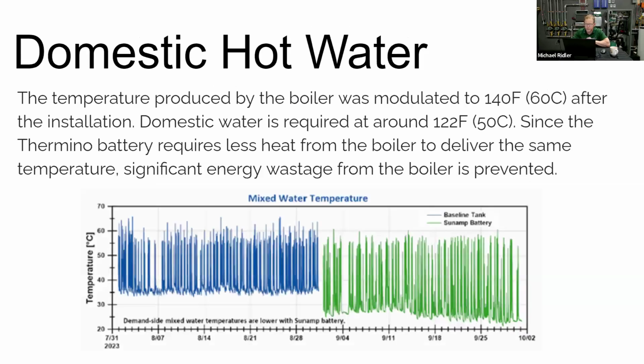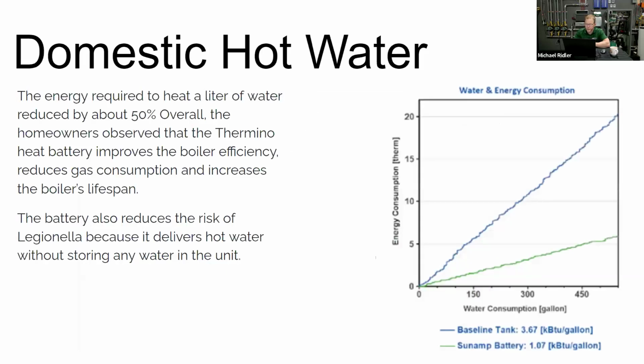If we go on to the next graph, we can also see from a domestic hot water standpoint that we were actually able to deliver more water, with the unit running less, because the standby losses were insignificant compared to the indirect. So at a lower water temperature with lower boiler running time, they were able to deliver more water than before, and the boiler was cycling less, running more efficiently. So it's pretty cool from that standpoint.